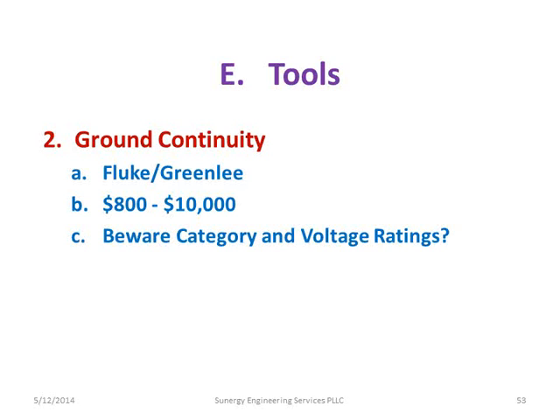So it's nice to be able to confirm continuity, because we have a pretty complicated grounding system with a lot of different connections in it. It's good to be able to confirm that you have a good ground all the way down to the ground. It's going to be important for your safety, and it's going to be what makes sure that your breakers go off when they're supposed to, that you have a good ground. And of course, if you're doing live testing, you want to make sure you have a good ground before you start touching stuff.